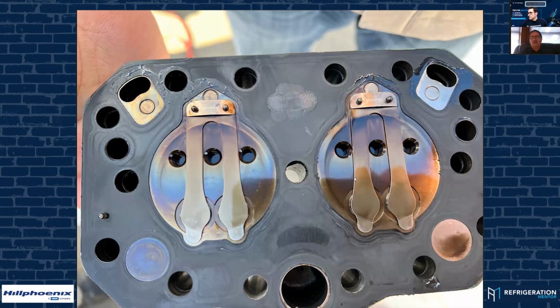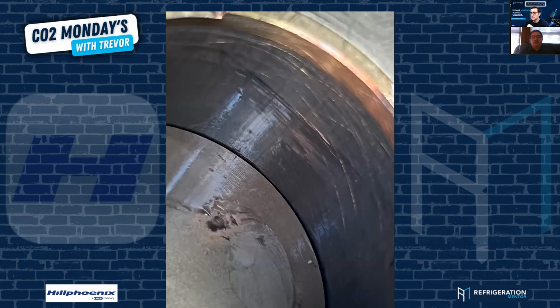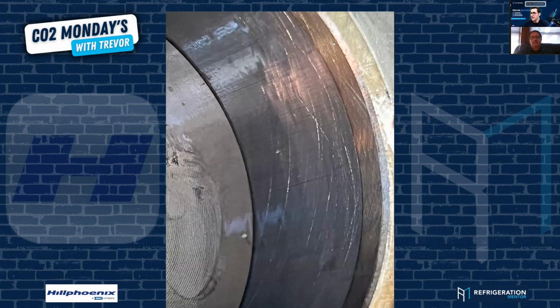There's one check that you can do, and this is the most important check that most people on compressors don't do, is your discharge line temperature check. Yep. So I was really surprised not to see any baking in the cylinder. Usually you'll get a yellow glaze once you start baking that oil, and then it ruins your honing, and you're not able to retain your lubricity for your cylinder. So usually you'll get striations in the cylinder, but I guess it was too short of a time, but the cylinders still look good. That's why originally I was good to go with just replacing the heads until we started it back up. Yeah, so there's a few more.